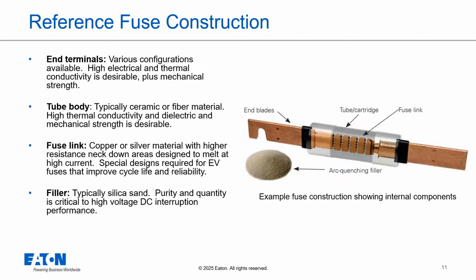The heart of the fuse is the fuse link. This is typically made of copper or silver. It has intentionally narrow sections called neck down areas, which are designed to melt precisely at high current levels. EV fuse links have special designs to improve cycle life and reliability given the demanding conditions. Inside the body, you'll find a filler, typically silica sand. The purity and quantity of this sand are absolutely critical for effectively interrupting high voltage DC faults.